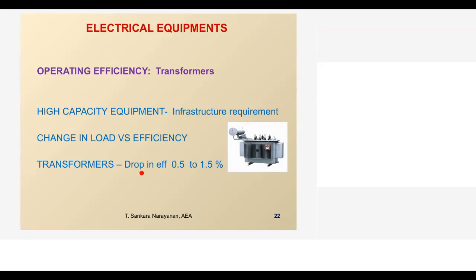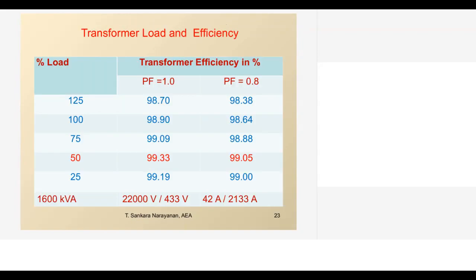If the operating efficiency drop is less, what can the auditor do? Because the operating efficiency drop purely due to load is small. This is a typical efficiency of a 1600 kVA, 22 kV per 433 volt transformer. So primary ampere is 42, secondary is 2100. The transformer manufacturer always gives all these details: 25% load, 50%, 75%, 100% and 125% load. The transformer is tested for unity power factor as well as for low power factor of 0.8.